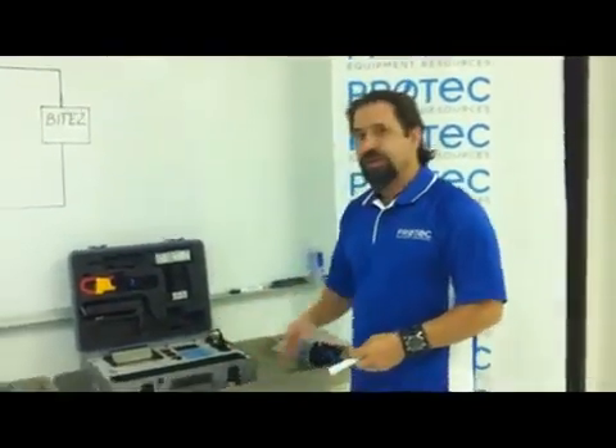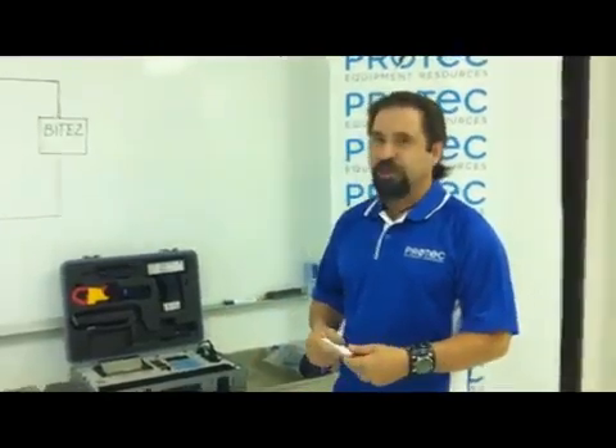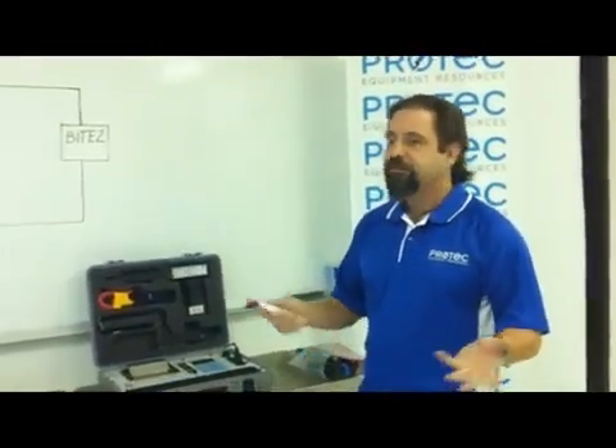Today I'd like to take you through the Megger BITE Model 2P. BITE stands for Battery Impedance Test Equipment, and the instrument we're demonstrating today is designed to test the state of health of standby battery systems, whether they're flooded, sealed, NiCAD, or lead-acid.